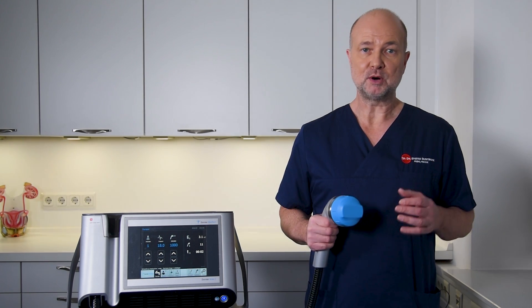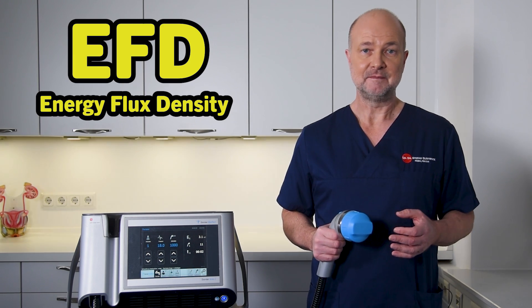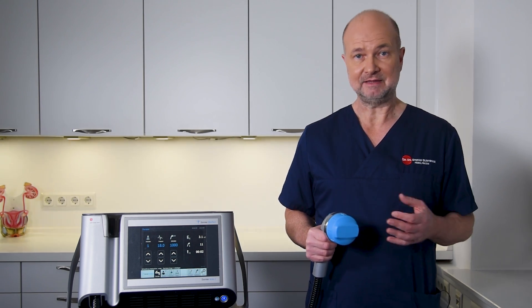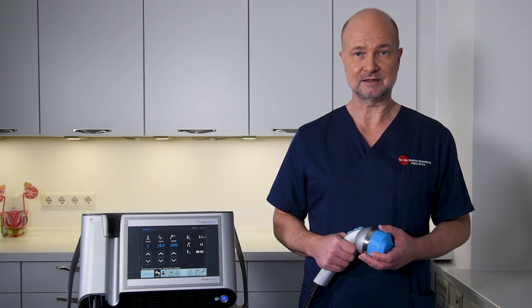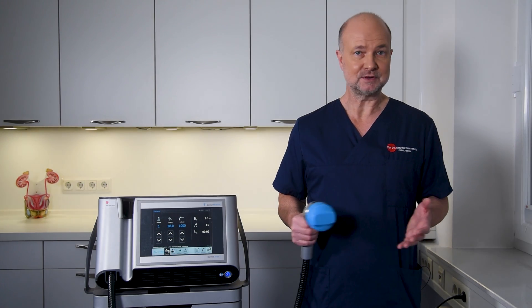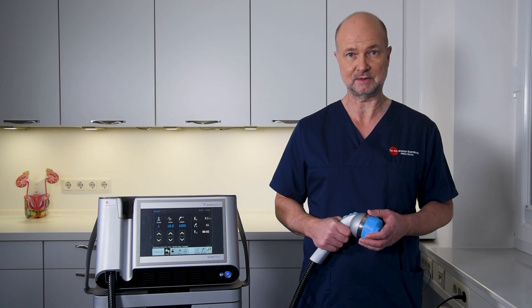One of the most important parameters for energy output is the EFD, the Energy Flux Density. The unit is millijoules per square millimeter. When looking at the studies that have been performed and the observed effects, the minimal energy needed to achieve any effect on erectile dysfunction appears to be 0.09 millijoules per square millimeter. I have tried different energy levels, sometimes I go a little higher, but usually I set the machine to 0.096 millijoules per square millimeter. It proved to be a very effective level.